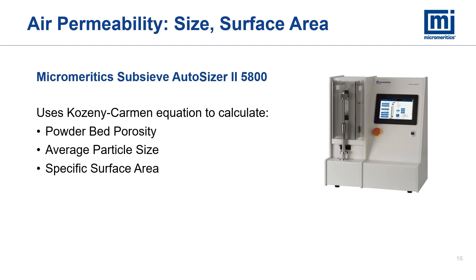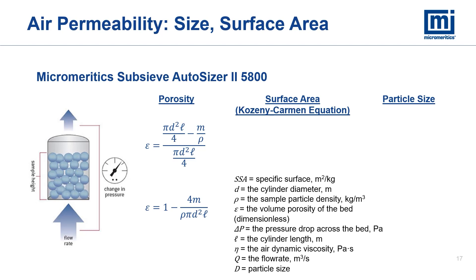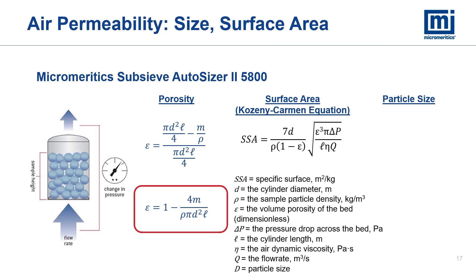The Micromeritics Sub-Sieve Autosizer 2-5800 uses air permeability and the Kozeny-Carman equation to calculate powder bed porosity, average particle size, and specific surface area. The amount of sample needed is equivalent to one cubic centimeter of skeletal volume. We used the density value calculated from the AccuPyc analysis to determine the mass needed. A powder bed is compressed to a certain height and a bed porosity is calculated. A constant airflow is applied to the bottom of the bed and the pressure drop across the powder bed is used to calculate specific surface area using the Kozeny-Carman equation. The density is then used to determine the average particle size.